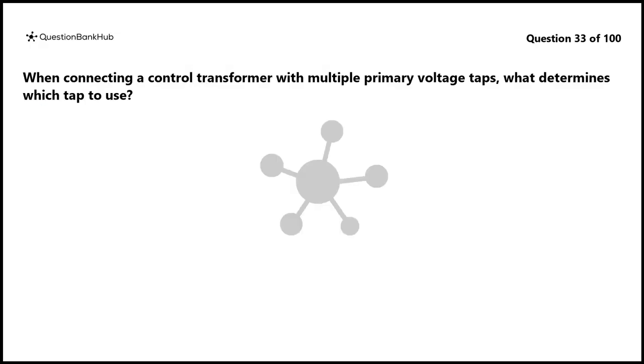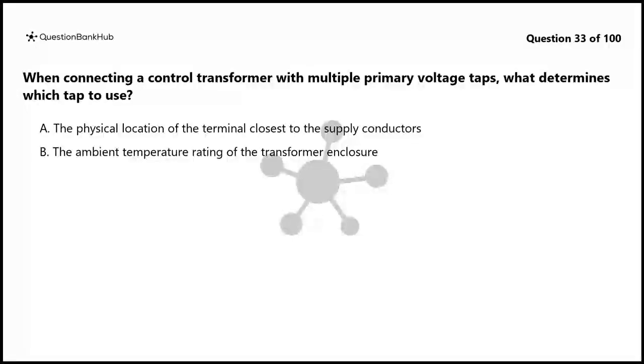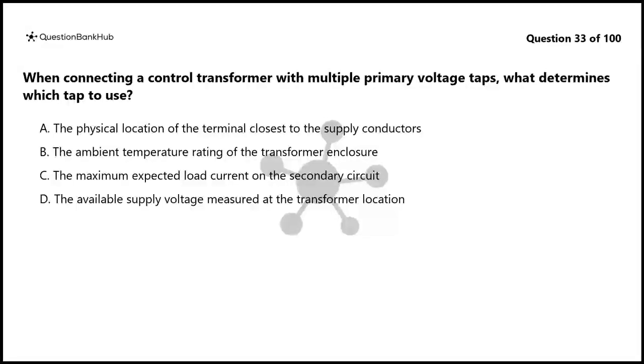Question 33. When connecting a control transformer with multiple primary voltage taps, what determines which tap to use? A. The physical location of the terminal closest to the supply conductors. B. The ambient temperature rating of the transformer enclosure. C. The maximum expected load current on the secondary circuit. D. The available supply voltage measured at the transformer location.